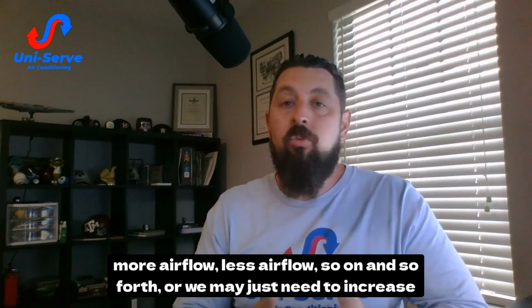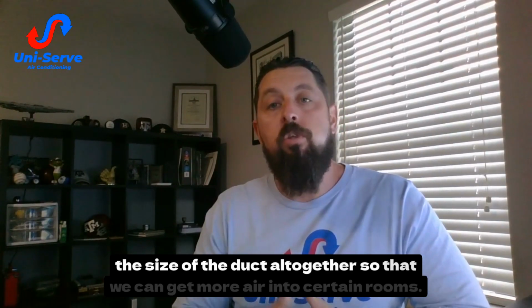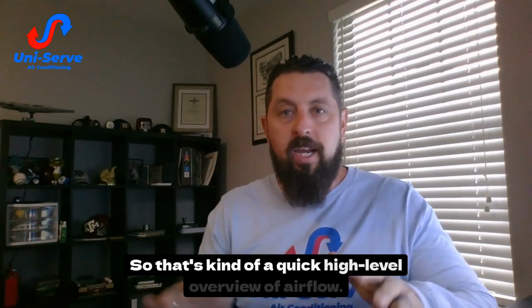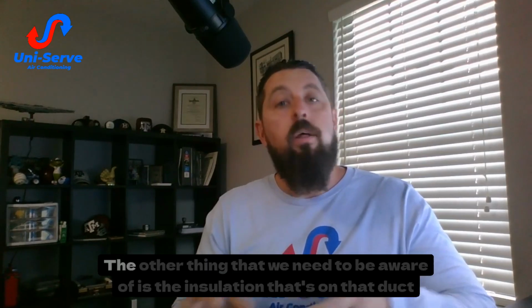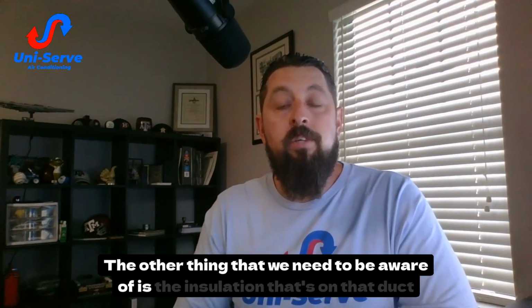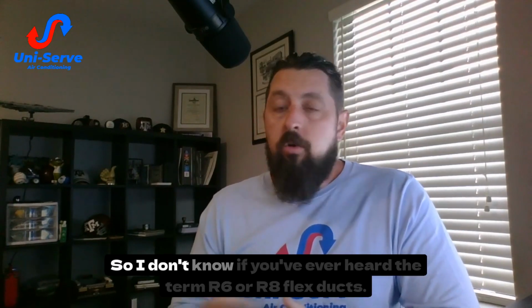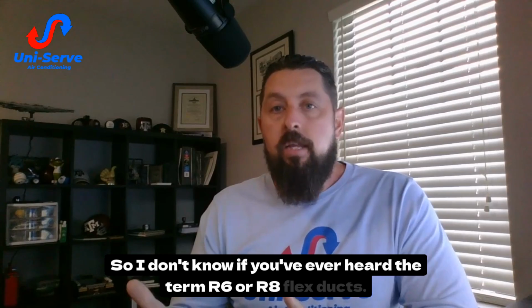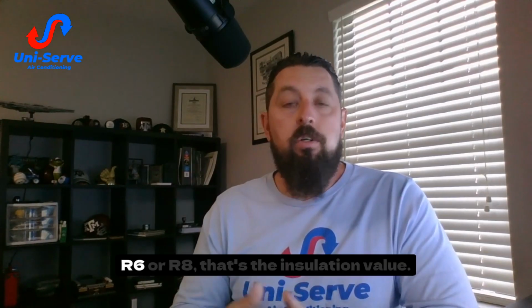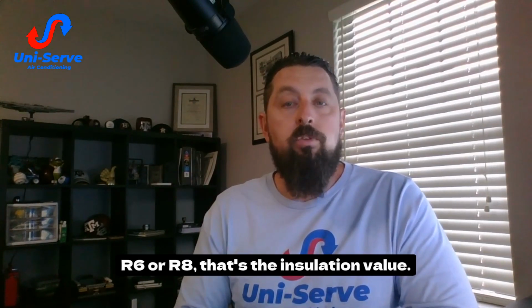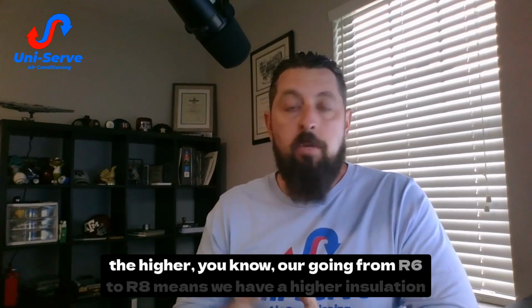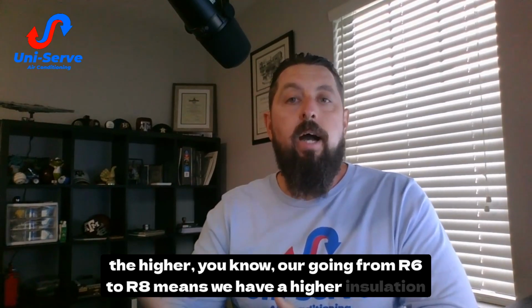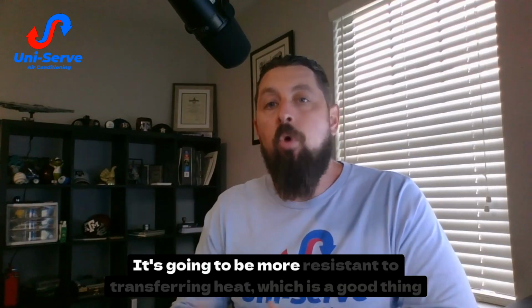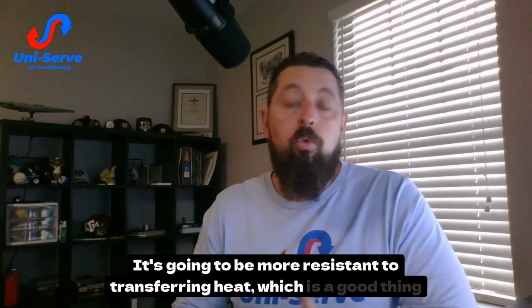Or we may just need to increase the size of the duct altogether so that we can get more air into certain rooms. So that's kind of a quick high-level overview of airflow. The other thing that we need to be aware of is the insulation that's on that ductwork. I don't know if you've ever heard the term R6 or R8 flex ducts. That's the insulation value. Going from R6 to R8 means we have a higher insulation value. It's going to be more resistant to transferring heat, which is a good thing.